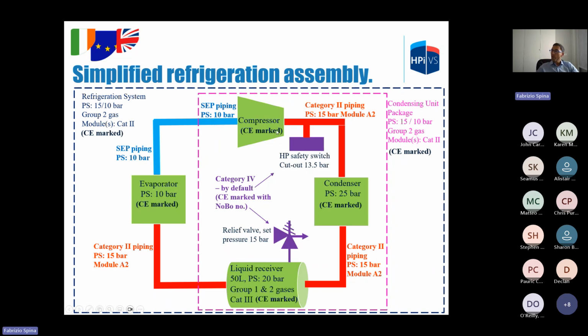We have the compressor with a discharge pressure of 15 bar in that example. So the high side is 15 bar, the low side is 10 bar. Once the allowable limits for the assembly are defined, we need to verify that each component has an equal or higher PS than 15 or 10 bar. So the condenser is 25, so it's okay. The receiver is 20 bar, so it's okay, and the evaporator is 10 bar on the low side, so that's okay.